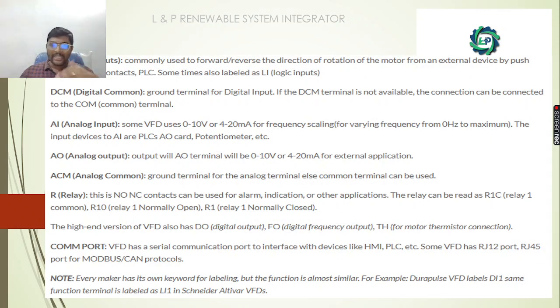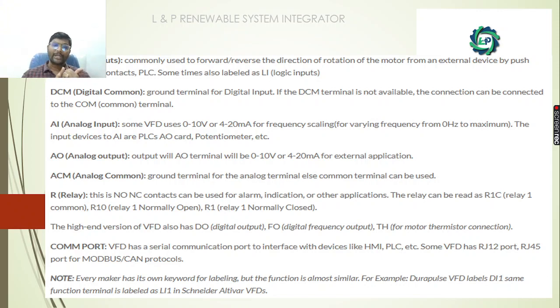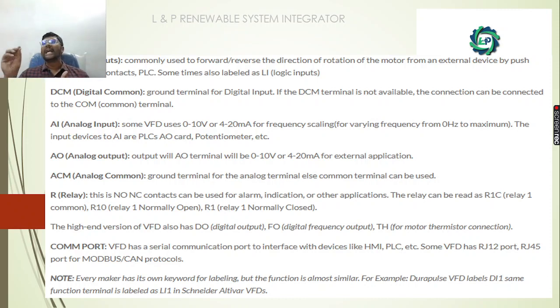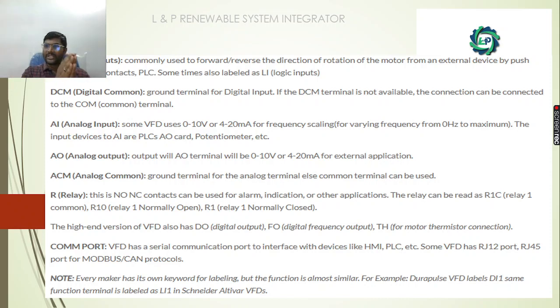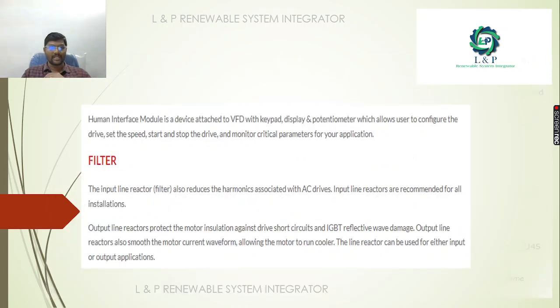Going more in-depth, we have digital input modules, digital output modules, analog input modules, analog output modules, relays, and a communication port for the VFD to communicate. For the analog input and output, we are using 0 to 10 volts or 4 to 20 milliamps based on our requirement. It will be going either to the potentiometer or to the PLC analog module. Similarly for analog output, we will have 0 to 10 volts or 4 to 20 milliamps availability for controlling external applications. For the relay, we will have normally open and normally close contacts, and based on our requirement we can use the concerned relays.